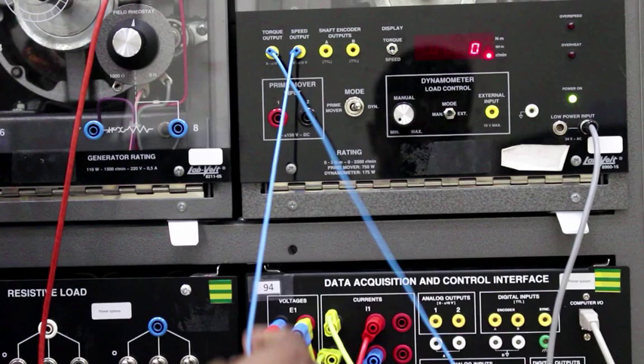And also, because we want to control IF here, you should connect the rheostat resistor in series. Of course, don't forget to turn off the power. Connect the rheostat resistor in series with the field winding, so we can change the value of the current rheostat. Sometimes the value of the resistor is not enough, so just in case, I'm gonna connect a resistance from here also, to increase the value of the rheostat.